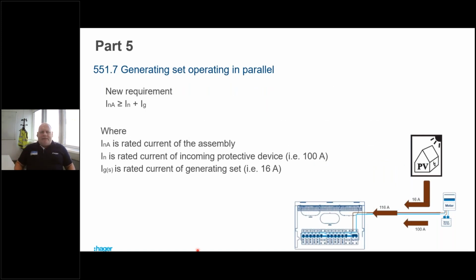Okay, this one is a new regulation, a new requirement. So a generating set operating in parallel. We've had them for a long time. We've had PV installations feeding into a board for 20 years. But we've now looked at it and said we need to meet this new regulation, where it says INA is greater than or equal to IN plus IG.